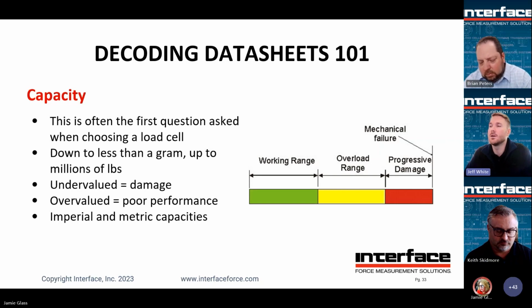You can kind of see how we graph it here. You start with the working range, which you want to normally stay within. The overload range, you can certainly go into the yellow there. You don't want to live in the yellow, but once you get into the red, you might damage the load cell so that it will no longer perform. And once you go past that, you might have a load cell that breaks in half.